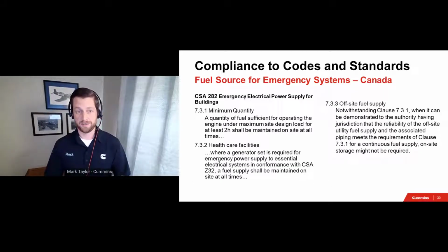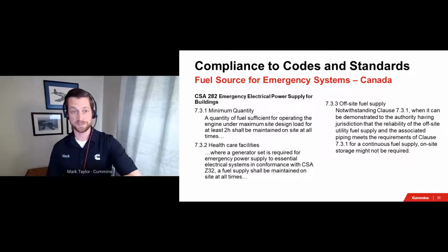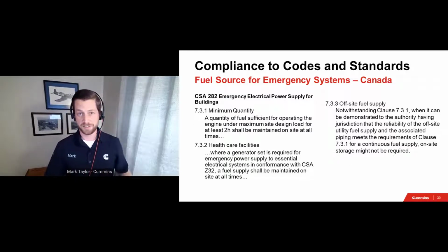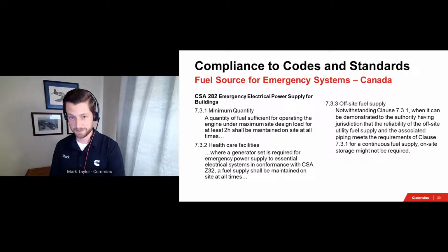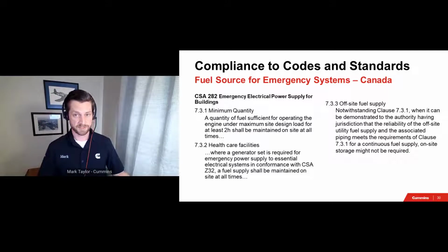Quickly switching gears here, having just covered NFPA 110 requirements, I would like to dedicate at least a slide to focus on the CSA language for our Canadian audience members. CSA282 is the counterpart to NFPA 110, and there are a lot of similarities here. Regarding on-site fuel storage, you'll notice callouts to 2 hours of runtime under the maximum site design load, and the requirements go further for healthcare facilities. For healthcare facilities that fall under CSA Z32, a fuel supply shall be maintained on site at all times for at least 24 hours for Class B and C facilities and at least 72 hours for Class A facilities.